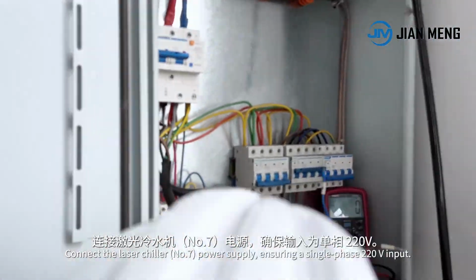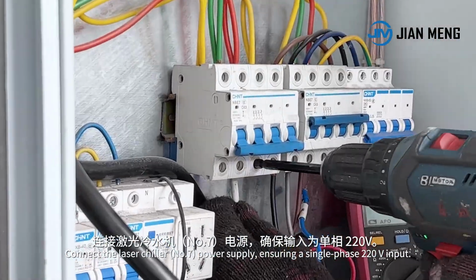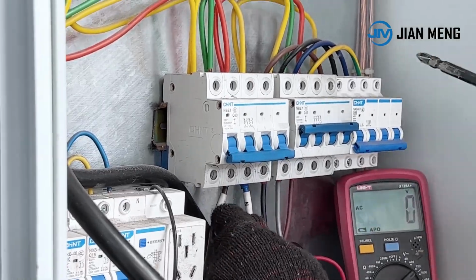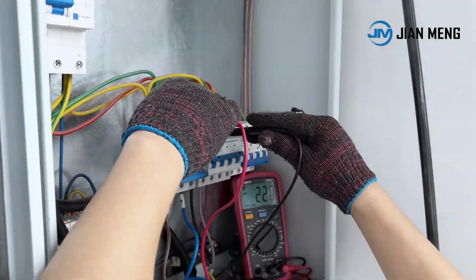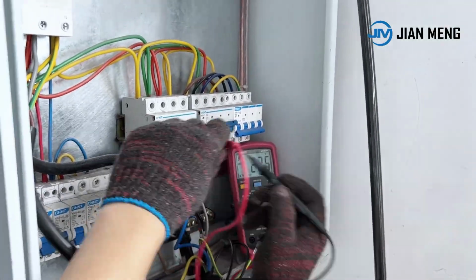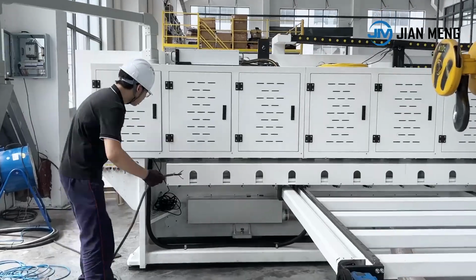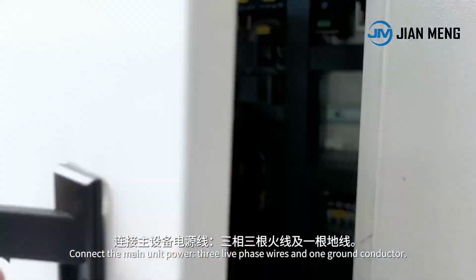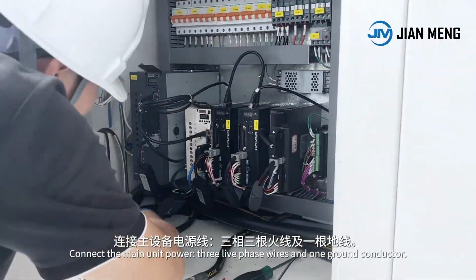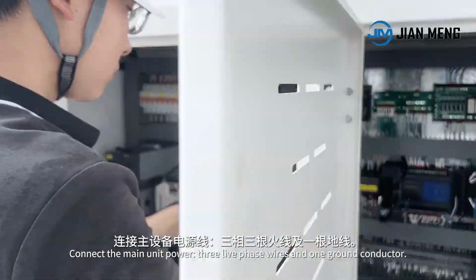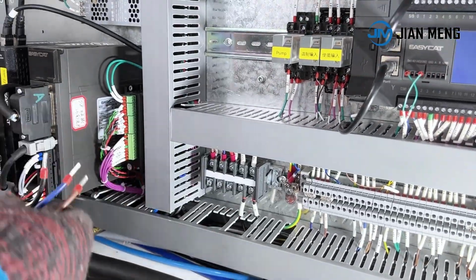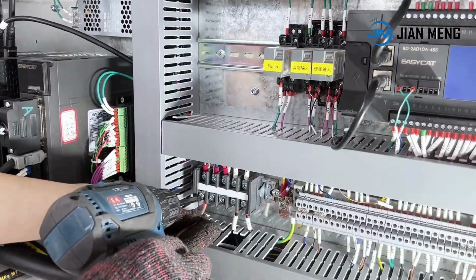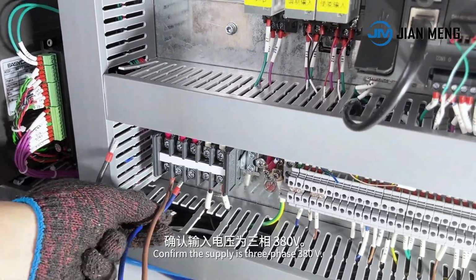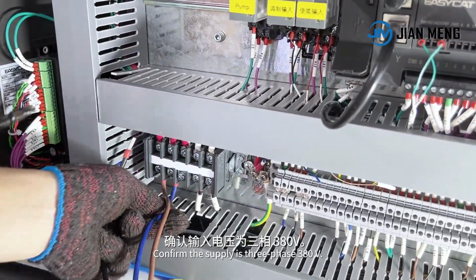Connect the laser chiller number 7 power supply, ensuring a single phase 220 volts input. Connect the main unit power, 3 live phase wires and 1 ground conductor. Confirm the supply is 3-phase 380 volts.